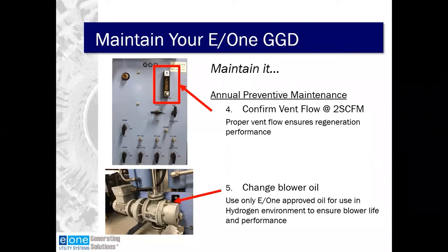And then the last step, as we noted the criticality of, is changing the blower oil. So even if you're on a quarterly cycle, when it comes time for the annual preventive maintenance period, you would be doing your fourth oil change of the year. It's important to note that we only want to use E/One approved oil, which is designed for use in the hydrogen environment, to ensure that the maximum life of the blower and the absolute best performance of that blower is attained.